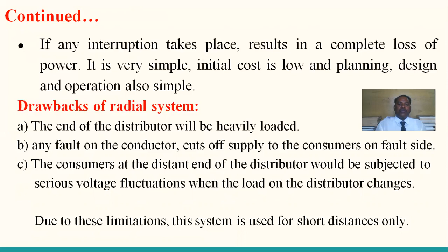And the second type of system is the loop or grid system. See here, loop or grid system. From the substation onwards, a single feeder, and every consumer or every load has more than a single path. Suppose any one path has an interruption, the other path will provide power for them. So this type of system is more complicated, but preferable for emergency loads like hospitals, commercial business centers, shopping malls. Such important loads only, this type of connection is to be prepared.